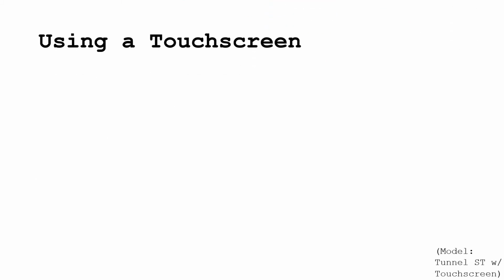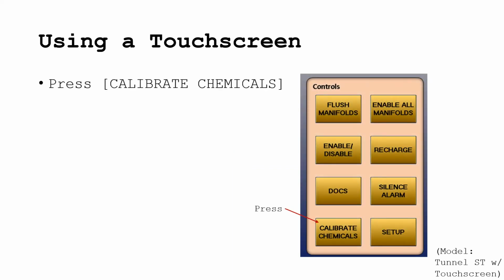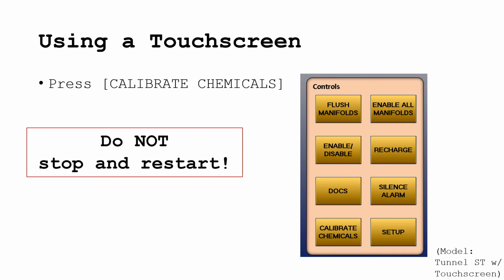If you are using a touch screen to calibrate, instead of holding down the Yes key, you press the Calibrate Chemicals button once to turn the pump on, and once again to turn it off. Remember, for accurate calibration it is important that you do not stop and restart the pump.